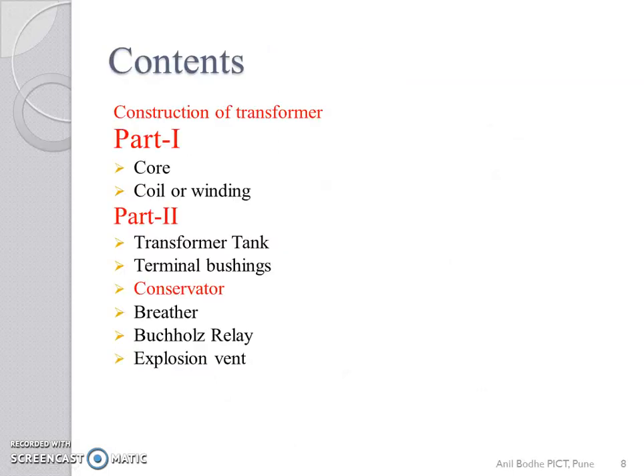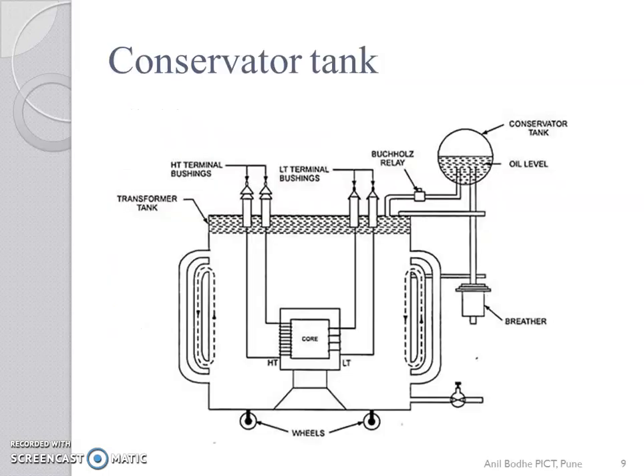Now, conservator tank or conservator. This is an airtight cylindrical metal drum mounted on supporting structure on the roof of the transformer main tank. This drum is connected by a pipe to the transformer tank and is always partly filled with oil. It provides mainly two purposes.